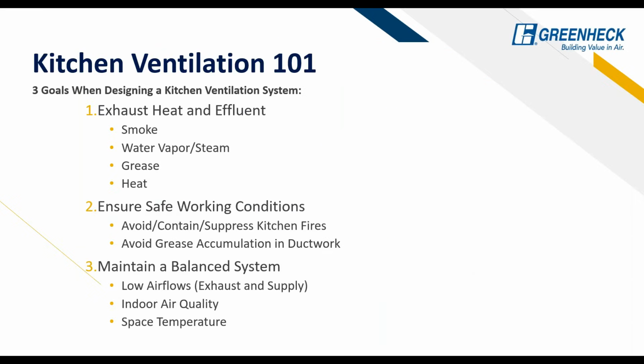So to start with kitchen ventilation, I like to start off with just describing the three goals of what a kitchen hood is. The first and foremost is to exhaust heat and the effluent, whether that's even the smells. We're just trying to keep that cooking heat inside the hood and get it exhausted out of the building.